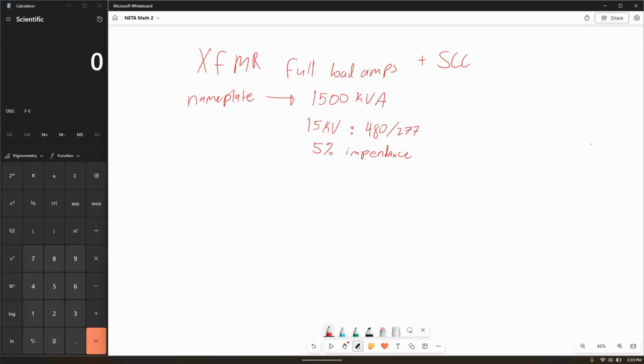This is the nameplate information that we're given, and I need to find out both the full load amps and the short circuit current. Now, the formula for full load amps, kVA per phase. Sometimes it'll be in VA. So this will be our VA divided by 3 times the secondary voltage. So now why do we divide it by 3? Well, assuming it's a 3-phase transformer, we need to get it down to the number of phases that we're actually looking at, because we get the full load amps per phase.